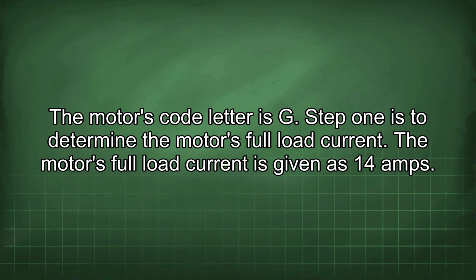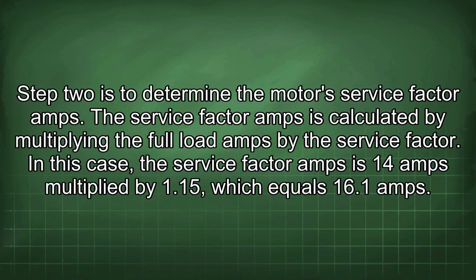Step 1 is to determine the motor's full load current. The motor's full load current is given as 14 amps. Step 2 is to determine the motor's service factor amps. The service factor amps is calculated by multiplying the full load amps by the service factor. In this case, the service factor amps is 14 amps multiplied by 1.15, which equals 16.1 amps.